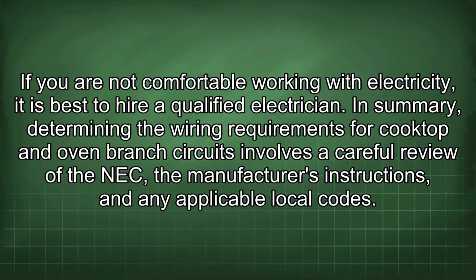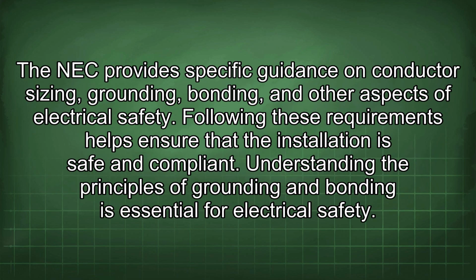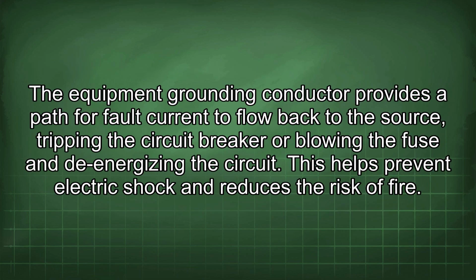In summary, determining the wiring requirements for cooktop and oven branch circuits involves a careful review of the NEC, the manufacturer's instructions, and any applicable local codes. The NEC provides specific guidance on conductor sizing, grounding, bonding, and other aspects of electrical safety. Following these requirements helps ensure that the installation is safe and compliant. Understanding the principles of grounding and bonding is essential for electrical safety. The equipment grounding conductor provides a path for fault current to flow back to the source, tripping the circuit breaker or blowing the fuse, de-energizing the circuit. This helps prevent electric shock and reduces the risk of fire.